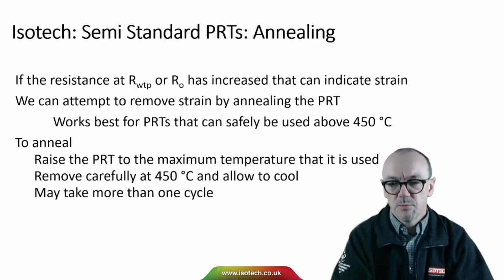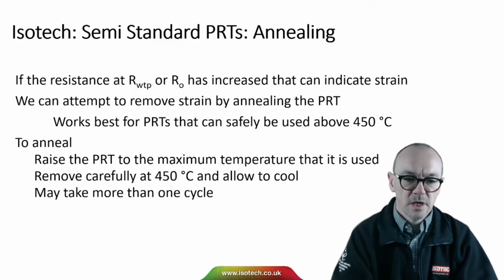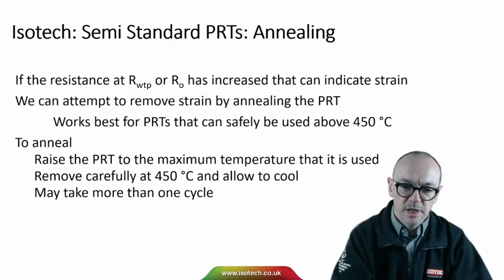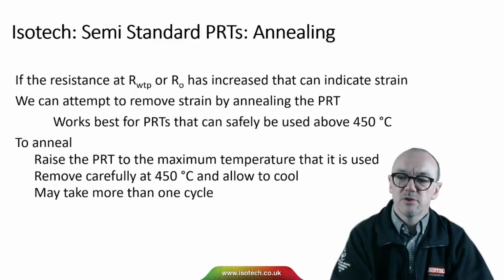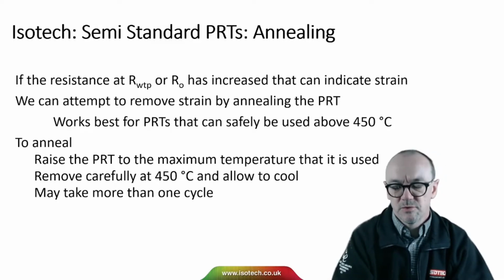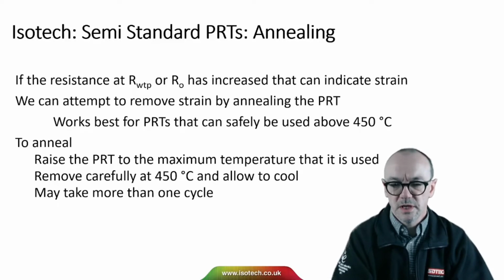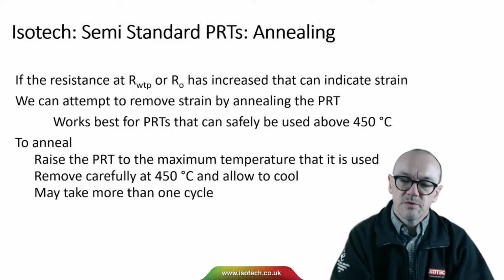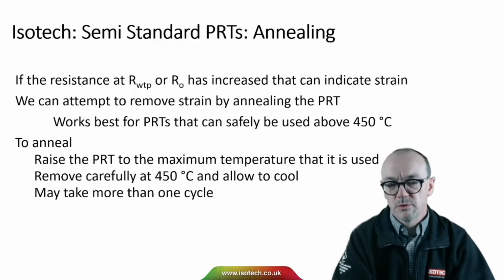Remember, you must never take a PRT higher than its maximum rated temperature. But for a PRT that can go to above 450 degrees C, the best way to anneal a thermometer would be to raise the thermometer to the maximum temperature that it's used, maybe 500, 600, 650 degrees C, and allow it to soak there for a period of time. Time's not so critical, perhaps a few hours, and then allow the thermometer to cool to perhaps 450 degrees C, and then the thermometer can be removed and allowed to cool.